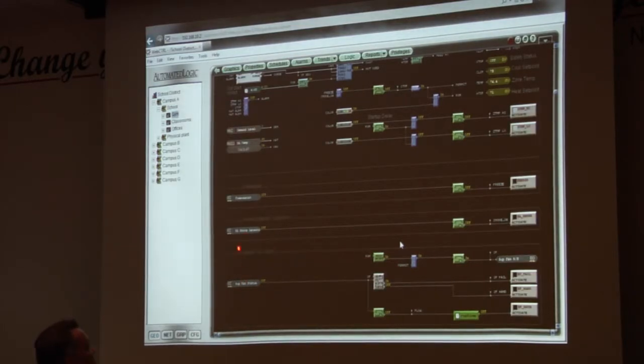So if you look down here, you see these 3 gray hot dogs. This one says BI for binary input. Same thing here. It has a little icon underneath of a set of contacts, all right? This one up here, if you notice, it says ANI, and it has a picture of a thermometer. That's an analog network input. Network inputs are coming from somewhere else in the system. Gray hot dogs are coming from a module. All of you are looking for an input, right? Temperatures are an input, so you know to look down the left side of the screen.